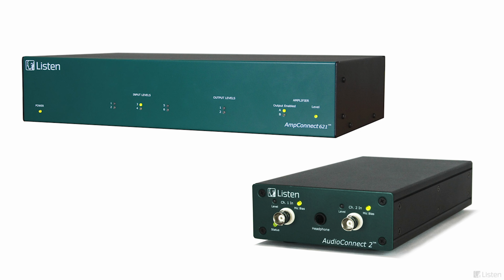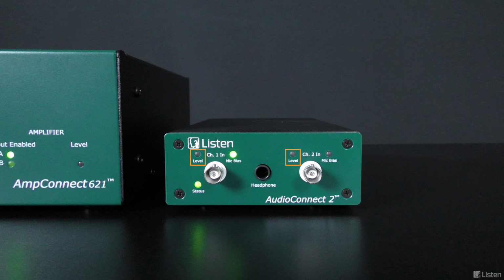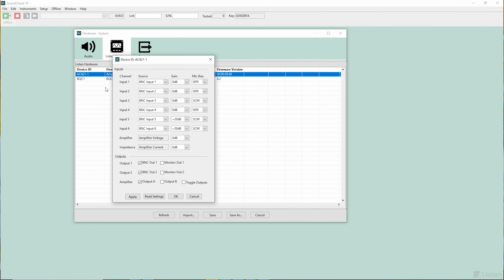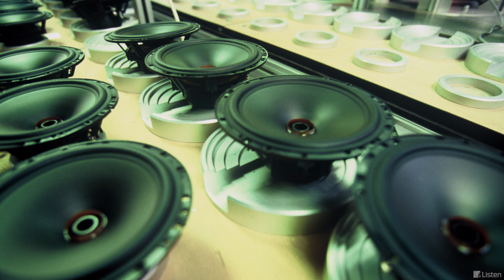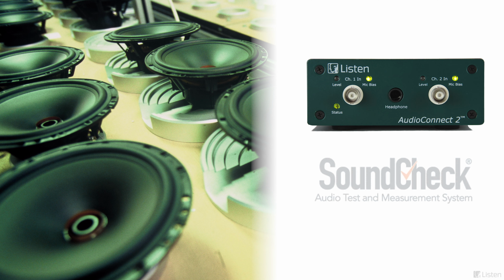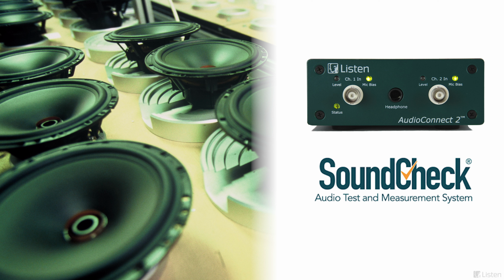You'll also notice something's missing: buttons. There are no knobs or buttons on the front panel, although we do have level and overload indicators, so you can be sure that everything is operating within maximum dynamic range. All control is via the software. This means that once you set your hardware configuration as part of your test sequence, no one can deviate from that at all, either by adjusting knobs or by incorrectly setting it up in the first place. This ensures that your test is being run correctly, and it's particularly useful if you are relying on third-party manufacturers to run your tests. If you specify the hardware, software, and test sequence, you can guarantee your product is tested to your exact standards with no room for error.